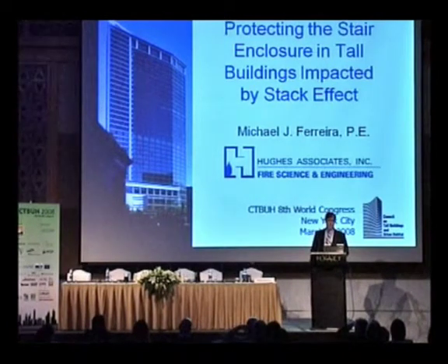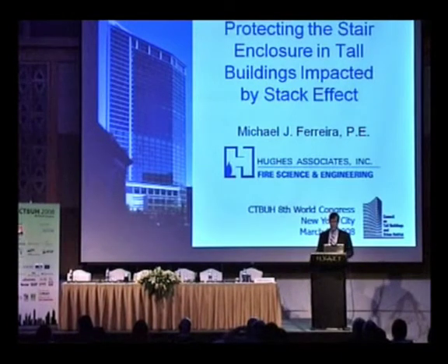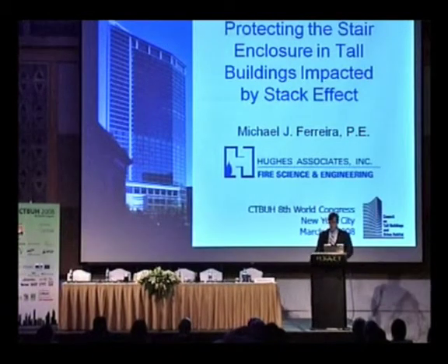It's a very significant building for me because in 1995 it was the first building where I was responsible as the engineer of record for the design of the smoke control and stair pressurization systems. It's also pertinent to this talk because it's a building where I almost lost my hand when the stair door slammed on me while commissioning the building, and we hadn't balanced the stair pressurization systems properly yet. So it is pertinent to this talk.